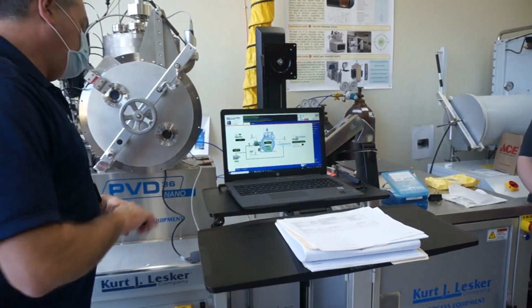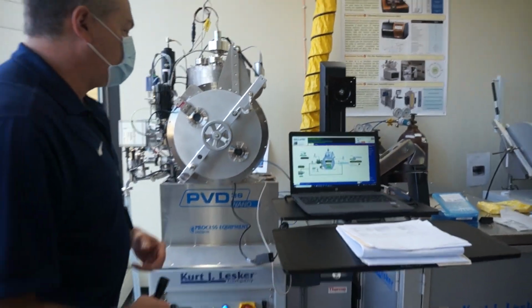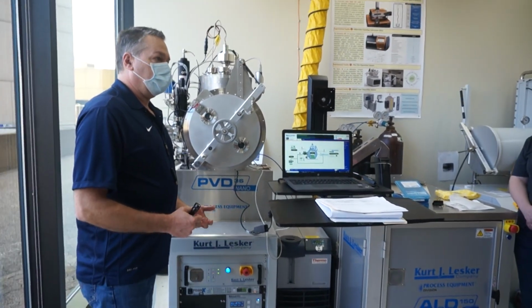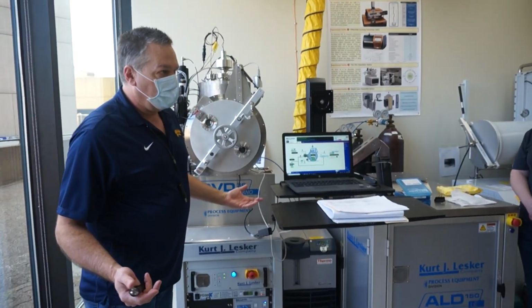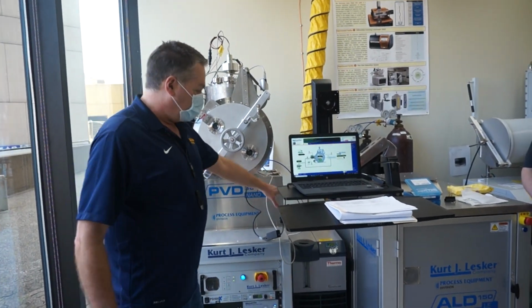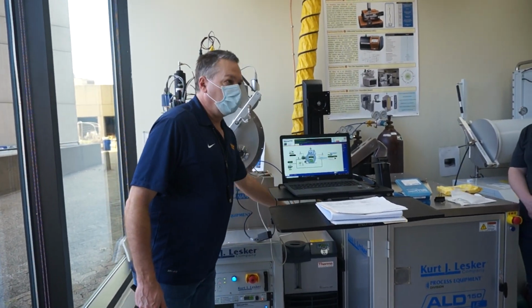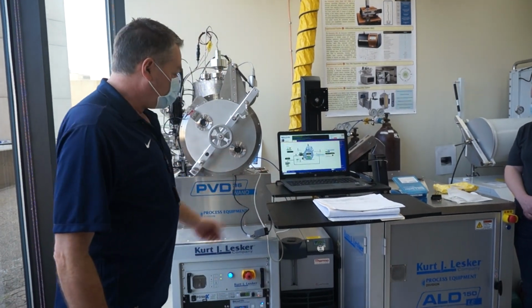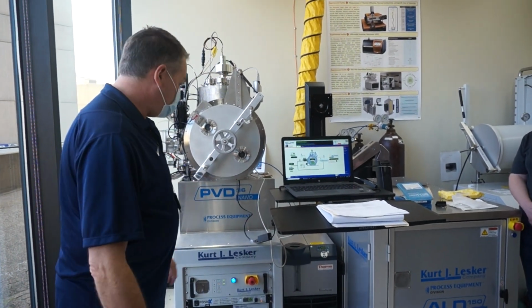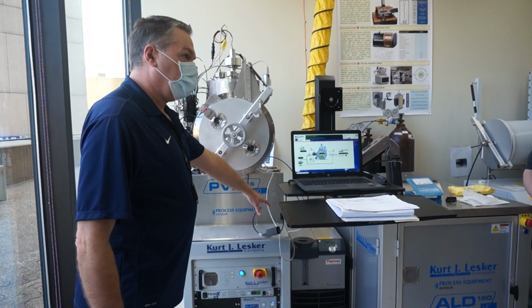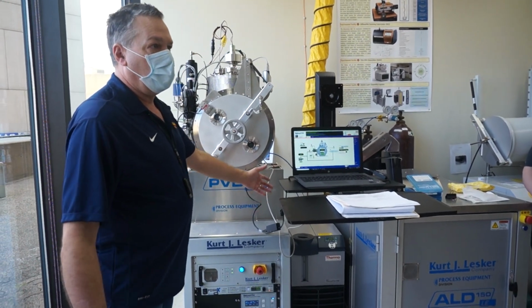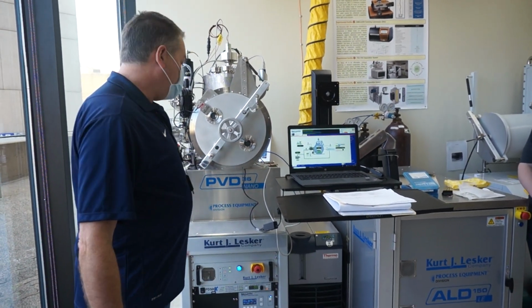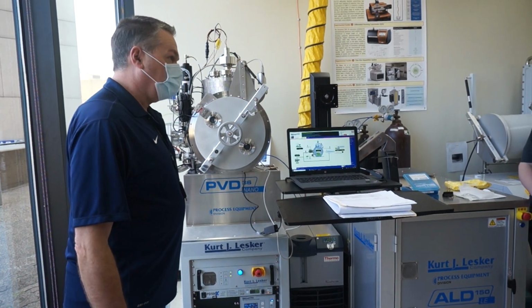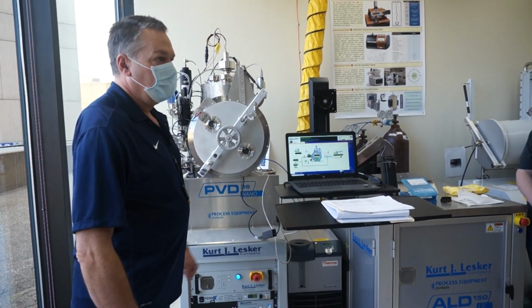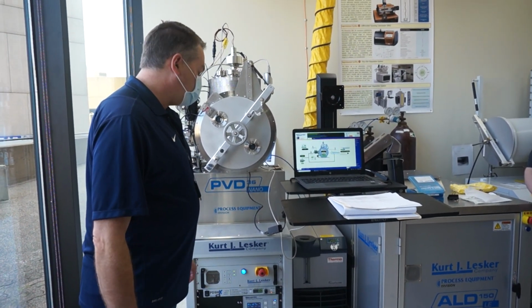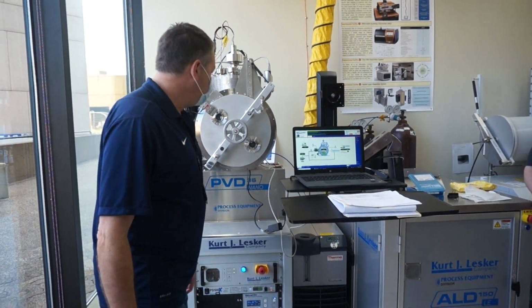Yes. So really what we want, we just don't want it to sweat whenever we vent the chamber. So we want it a couple degrees above the dew point. I don't know the workings of this controller, or else I would change it. But if it starts to sweat, you can pull out the manual. I don't know what type of water you're using. We usually use straight water, DI water. Yeah, and DI water. Okay. All right. I know at times you have to watch for algae or other contaminants within, but just keep an eye on the chilled water.